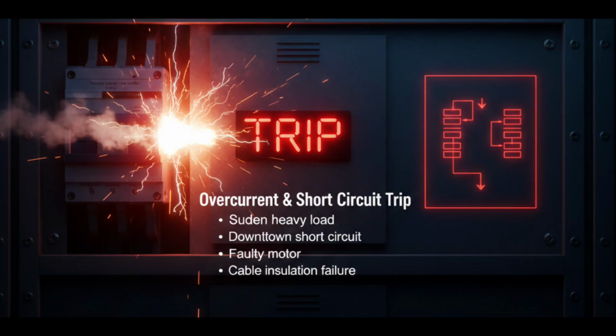Overcurrent or short circuit trip. If a generator suddenly trips on overcurrent, do not immediately reconnect it. First, ask, what changed? Was a heavy motor started? Was a crane or thruster engaged? Is there a downstream short circuit? Check feeder breakers one by one. Identify the faulty feeder. If a motor has insulation failure, reconnecting without inspection may cause repeated trip. Gradually restore loads. Never restore all loads at once. Overcurrent protection exists to protect cables and equipment from overheating and fire risk. Treat every overcurrent trip seriously. Find the cause, then reset.